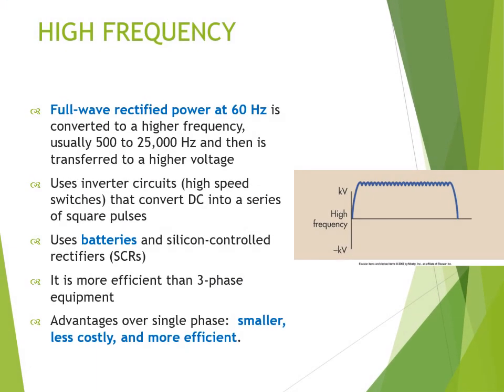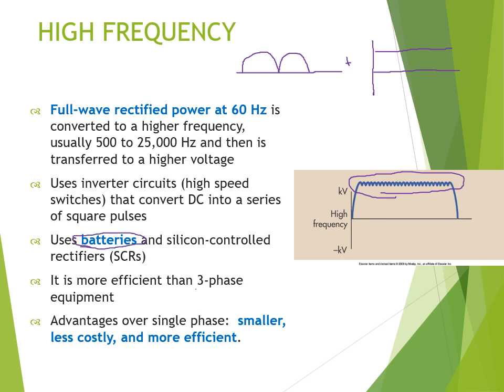So with high frequency, we're going to talk about how we are going to have high full wave rectified power, where we have 2 positive pulses, and we're going to add that to batteries. And batteries only have current flowing in one direction as well. So when you put those 2 together, we end up with a really, really tiny ripple of less than 1%. So it's using batteries and silicon-controlled rectifiers. It's much more efficient than 3-phase equipment. It's much smaller, less costly, and much more efficient.